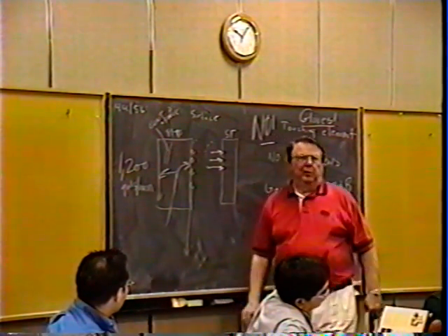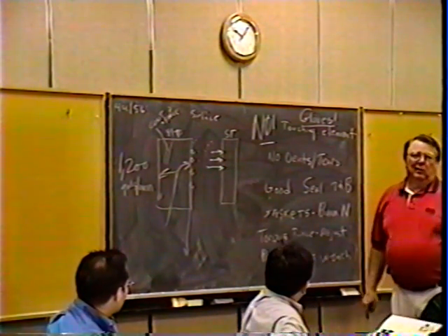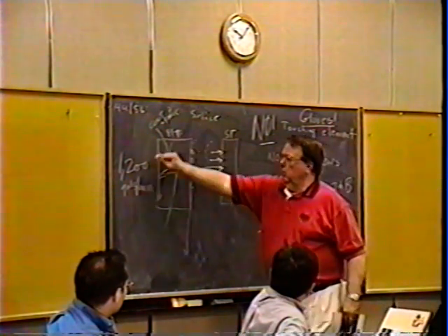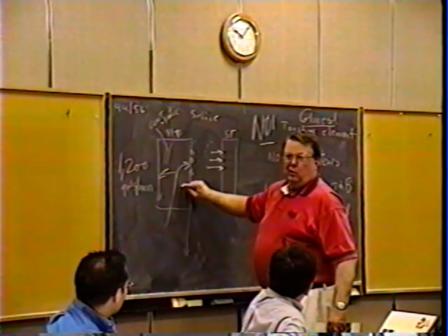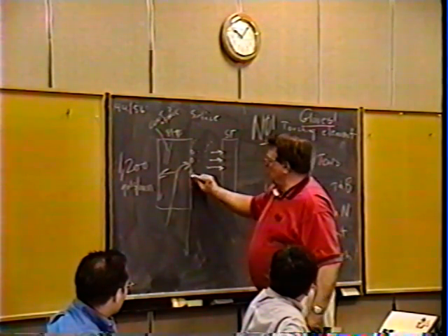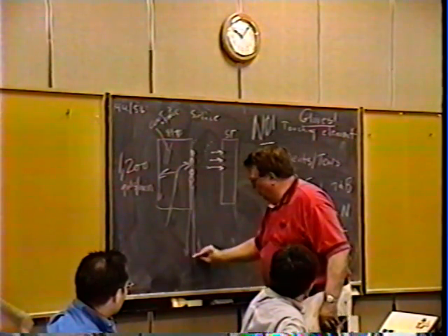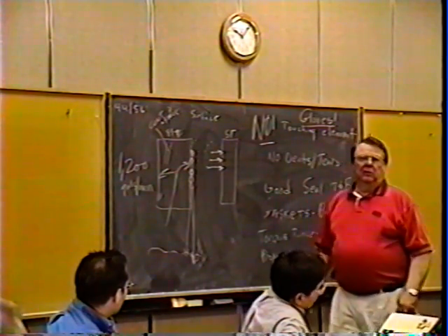So you can think of the velocity. We're shooting bullets at that Teflon separator, and that's not what it's built to do. This is the prime stopper for the water and the dirt. So by having nice big droplets, we're using physics that they're all going to go there, collect in the sump, and we're going to drain them.